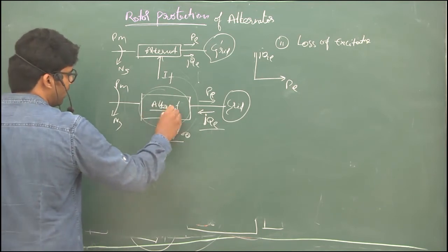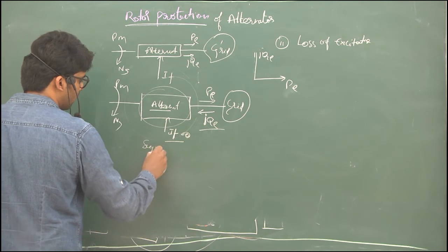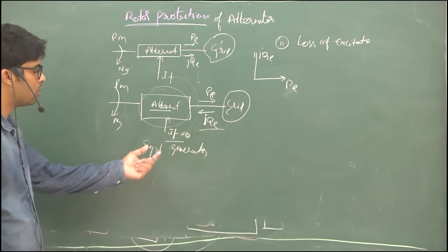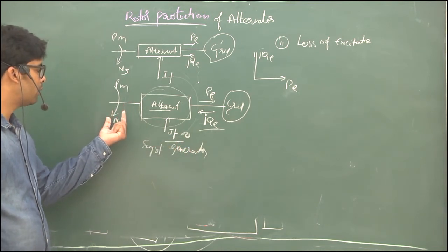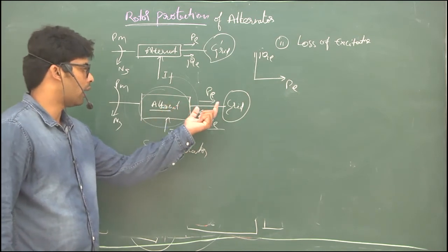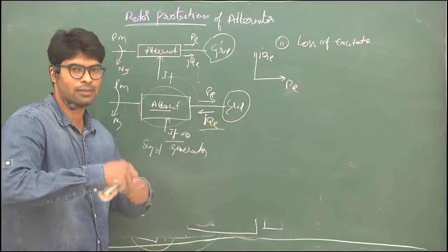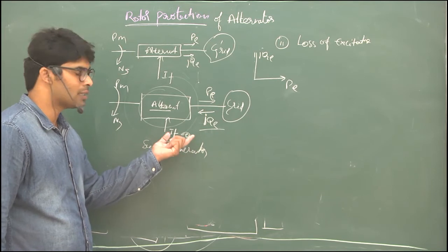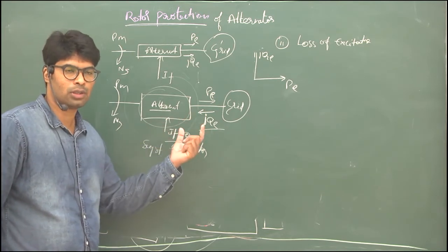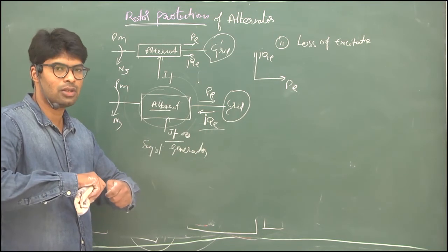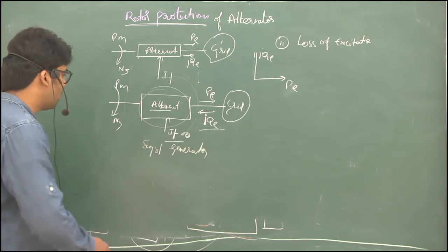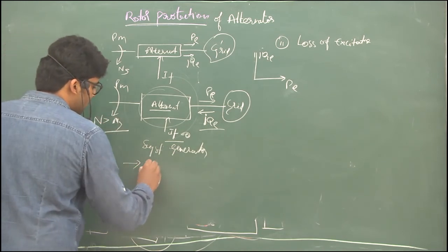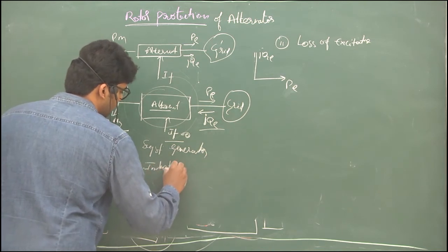And this time the alternator, instead of working as a synchronous generator, where the field produced by the excitation system and the field produced by the stator stay in a synchronous position and move in a synchronous manner to operate as an alternator, is different. Here the field given by the excitation system is 0. That is, there will be no drag force to hold it synchronous. Since there is no synchronism with the stator, the rotor will move with a speed greater than synchronous speed, that is, it will operate as an induction generator.